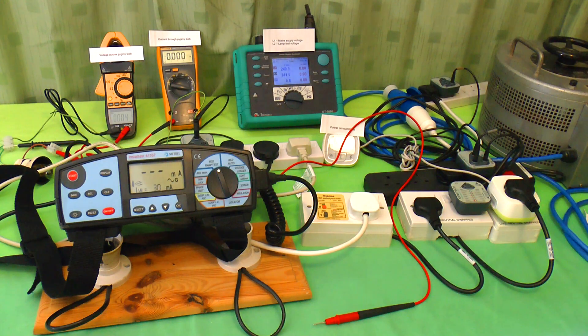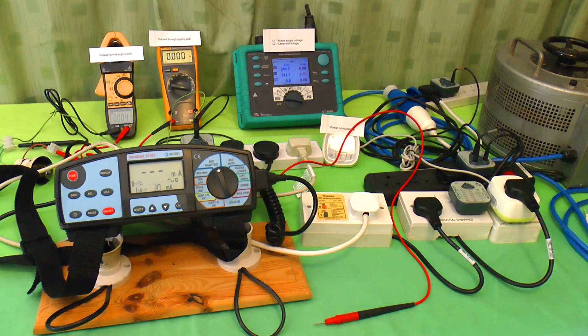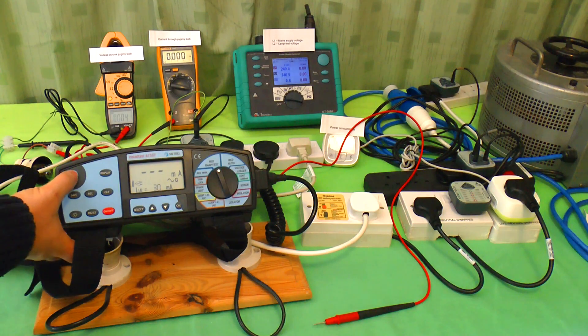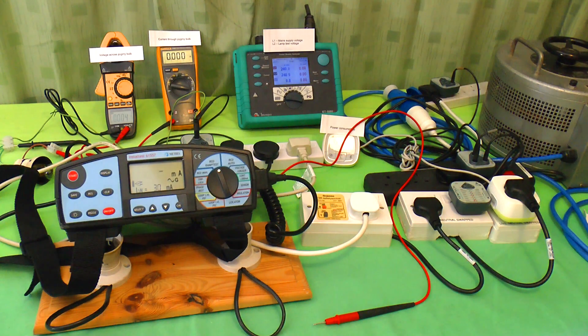Now, normally all of the current flowing in through the live wire flows back out through the neutral. If you touch something live, such as a cut lawn mower cable or a faulty appliance, some of the current will flow through you instead. Any more than a couple of milliamps and the RCD trips.